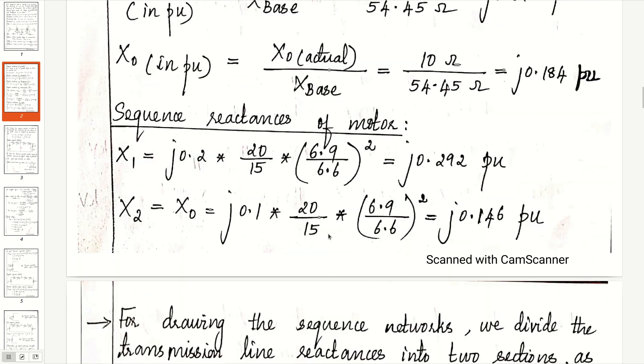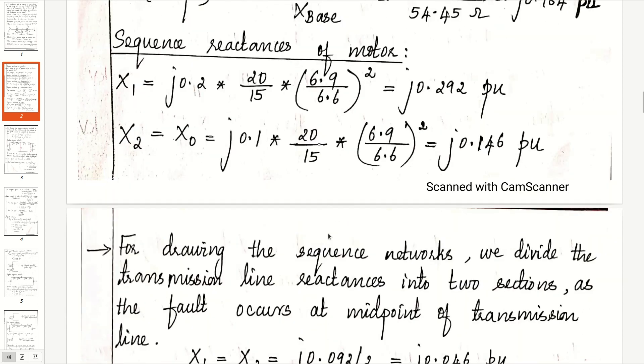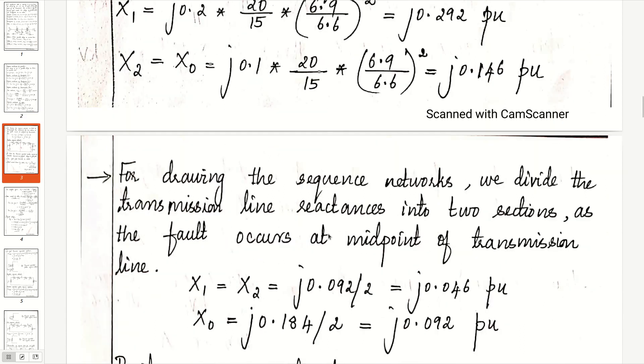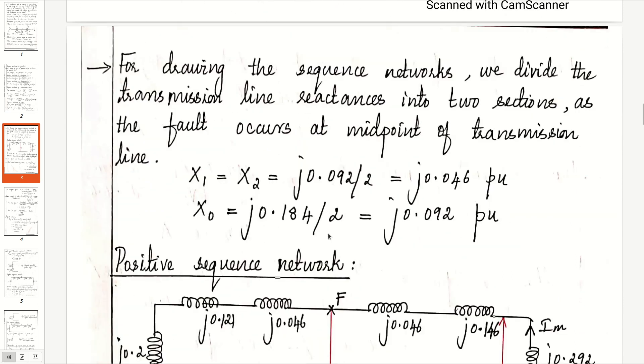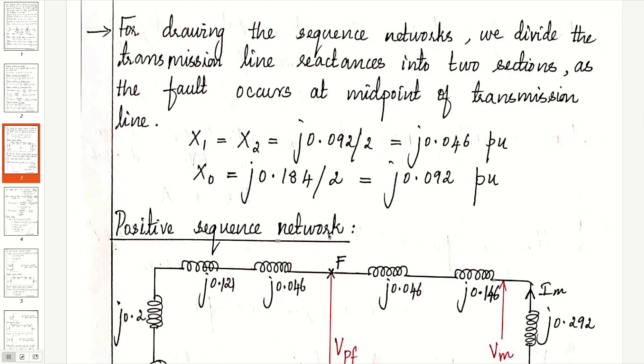For the motor, X1 is j0.292 per unit and X2 equals X0 equals j0.146 per unit. For drawing the sequence networks, we divide the transmission line reactances into two halves because the fault occurs exactly at the midpoint of the transmission line. So X1 equals X2 equals 0.092 divided by 2, which is j0.046, and X0 is j0.092 per unit.